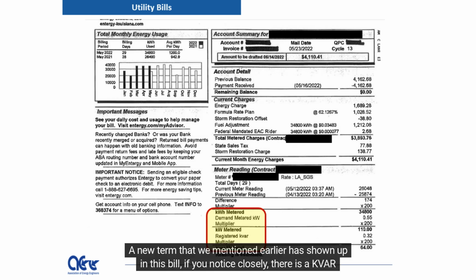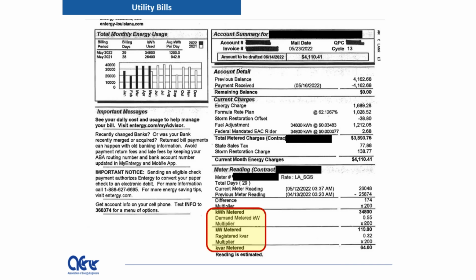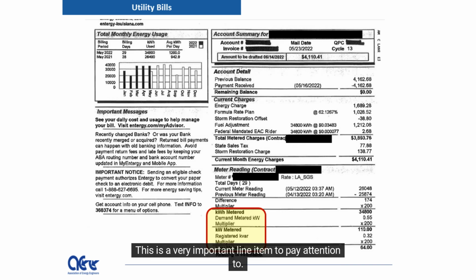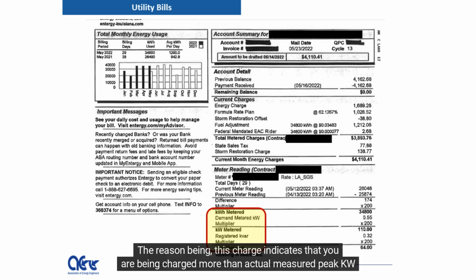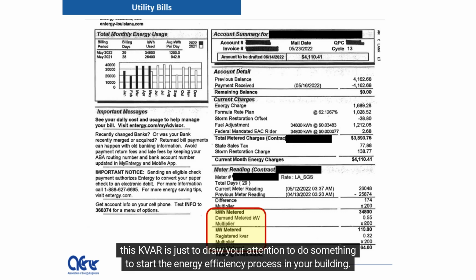A new term that we mentioned earlier has shown up in this bill. If you notice closely, there is a kVAR charge in this bill. This is a very important line item to pay attention to. The reason being, this charge indicates that you are being charged more than the actual measured peak kW in your bill. This kVAR is just to draw your attention to do something to start the energy efficiency process in your building.